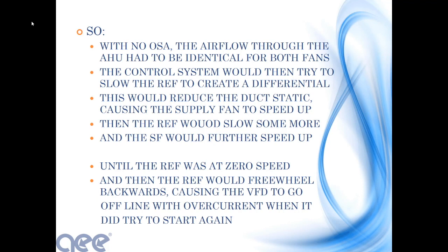Now, the control sequence that he was given was to simply use a speed differential. Supply fan at 50 hertz, we run the return fan at 45 hertz. And I have used this particular control sequence, which is dirt road simple. You don't need any airflow measuring devices. Oh, I got 50 hertz here. Let's see, what am I going to do? Oh, 45 hertz, okay. And you can dial it in.